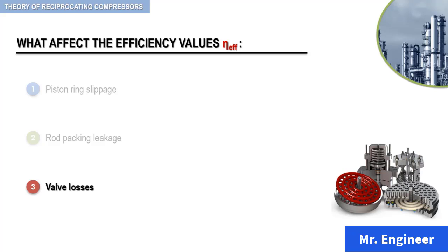Also, because of inertia and imperfect damping properties of the gas, the valve may have transient losses due to bounce. Therefore, the manufacturer modifies the valve lift to suit the gas specified. For example, an air compressor might be furnished with a lift of 0.1 inch, and the same compressor being furnished for a low molecular weight service such as hydrogen gas might use a lift of only 0.032 inches. Why is that? Because the problem with the higher lift is that hydrogen lacks the damping properties of air. As a result, the valve would experience excessive bounce. The effect on the compressor would be loss in efficiency and higher valve maintenance.